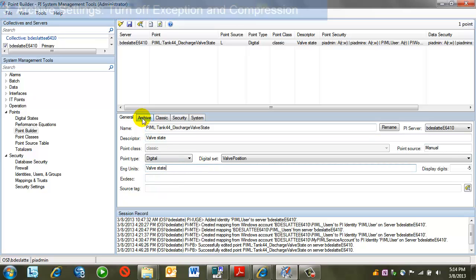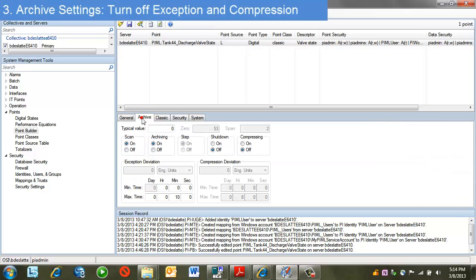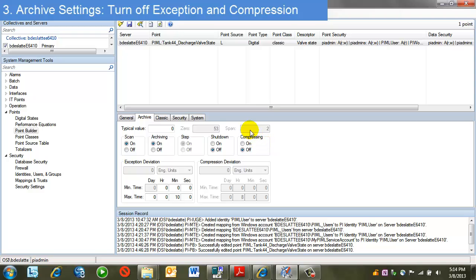Moving on to the archive tab. Two parameters of note here are compression and exception. In almost all cases, I will want all of my manual logger data to be stored in the archive. Therefore, I'm going to set compression off, exception deviation to zero.